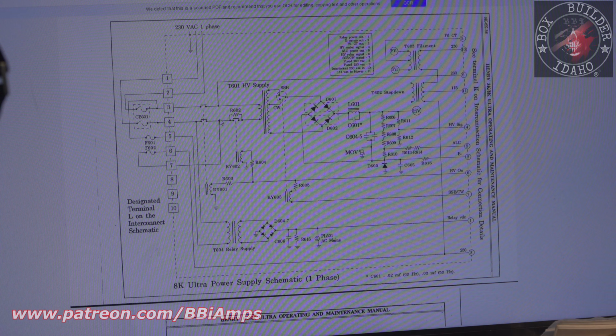After this second contactor fires, right here, we have a tap that comes out, goes through the second fuse, and it comes around, and this is what supplies the RF deck. Or pardon me, before it goes through this contactor, right here, it taps off, runs down, and that's what runs our remote head unit.